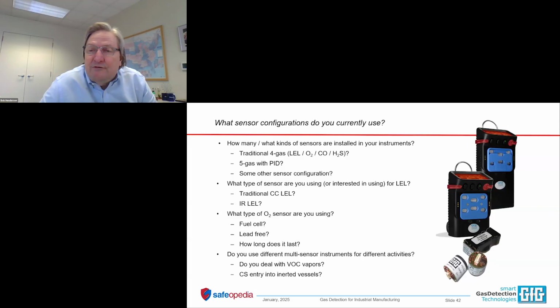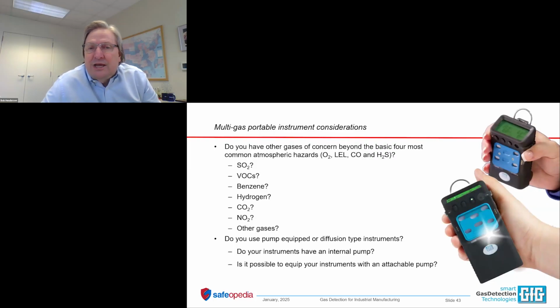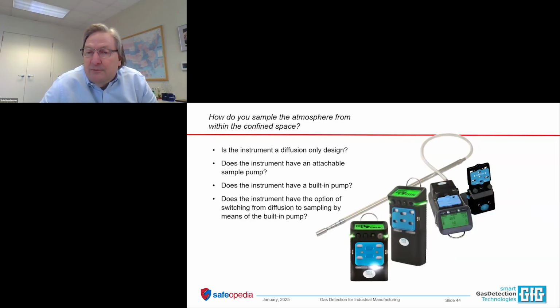So make sure that you have evaluated the need to have additional sensors or channels of measurement in the instrument if you have something else that is a concern. Sometimes it's SO2, sometimes it's NO2, sometimes it's cyanide, sometimes it's ozone. It can be just a wide variety of different analytes and contaminants. So that's also on the fixed detection questionnaire, a central question: What do you need to measure? That determines everything that follows. Do you use pump equipped instruments? If you do, consider whether you're better off with an attachable pump, a separately powered attachable pump, an internal pump, or if you don't need a pump, then a diffusion design.